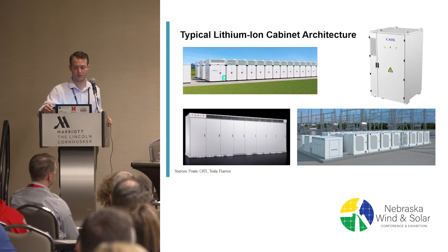One of the biggest advantages of this approach is to make the systems as prefabricated as possible. You used to have to ship the container on site because it was too heavy to ship with the batteries installed, then install the racks and modules after the container arrived on site, and then test it and certify everything on site. That drew out the construction period quite a bit, whereas when everything shows up tested and certified, it's a lot more plug and play this way.